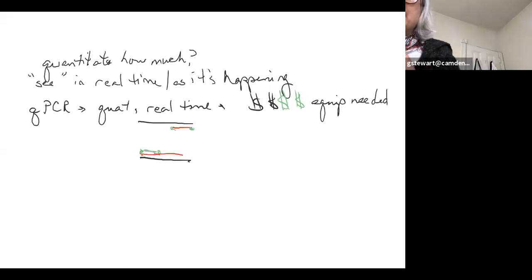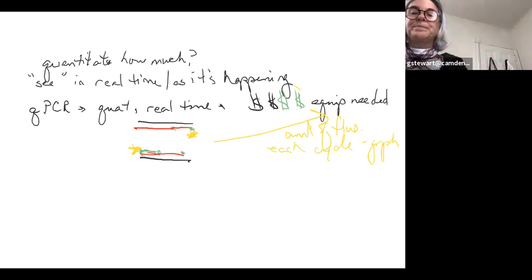But after the extension, when those 2 compounds get separated further, then one of them glows. It's fluorescence. And then this equipment measures the amount of fluorescence with each cycle. And it puts it on a graph. And you can watch it increase over time.